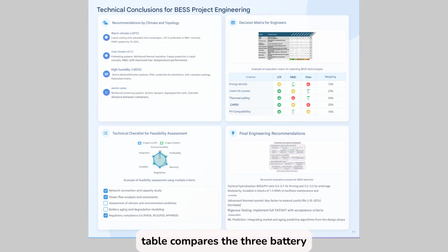The table compares the three battery technologies, LFP, NMC, and flow, according to 5 weighted technical criteria: energy density, lifespan, cycles, thermal safety, CAPEX, and PV compatibility. LFP technology is generally the most robust option for hot climates, high security projects, and integrated PV plants. Every BESS project must pass this checklist before entering the engineering phase to verify the grid connection and capacity study, the analysis of power flows and constraints, the climate and environmental assessment, battery degradation modeling, regulatory compliance, UL 9540A, IEC 62933, NFPA 855. This initial assessment avoids costly redesigns in later phases of the project.